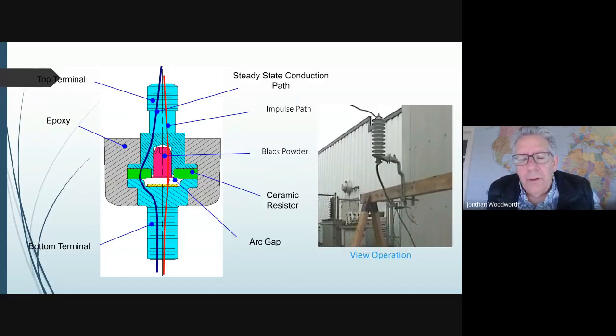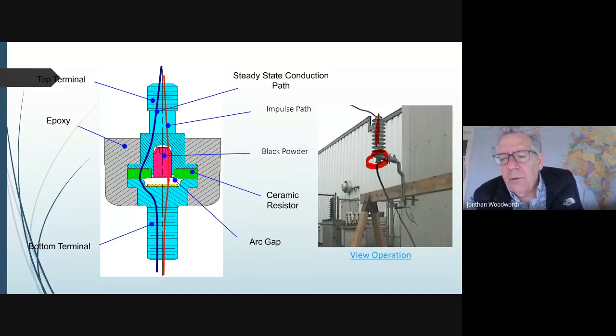Back to the ground lead disconnector on the bottom. Most distribution arrestors today have this device on the bottom, and the purpose is that if this arrestor should fail, for whatever reason, an animal got across it or moisture got inside, there are a couple different reasons why arrestors can fail. Maybe lightning was too high. That doesn't happen too often, but it can happen.